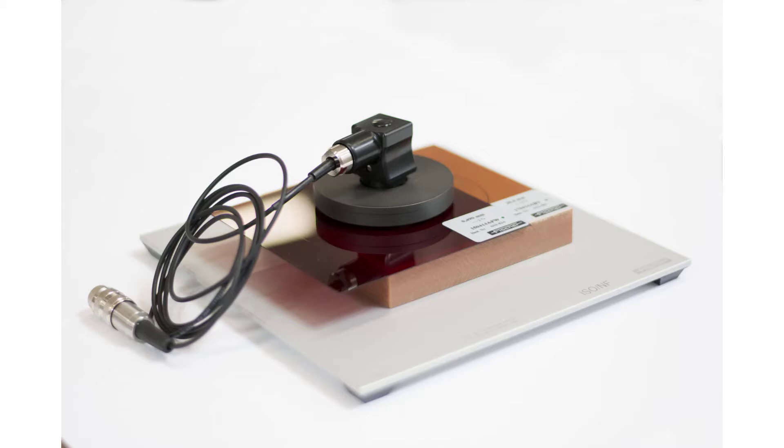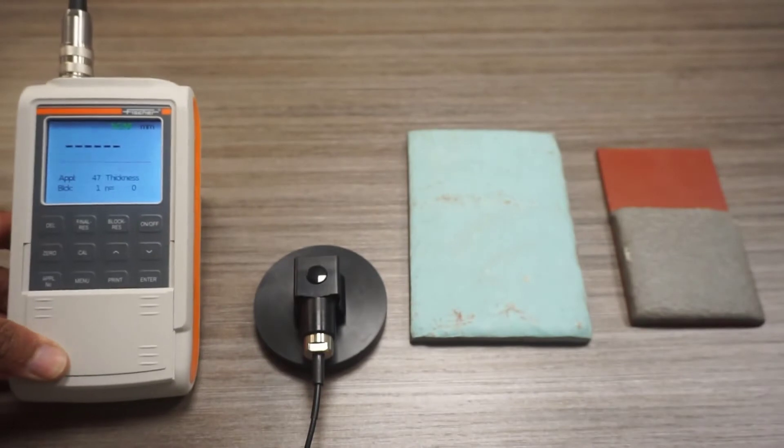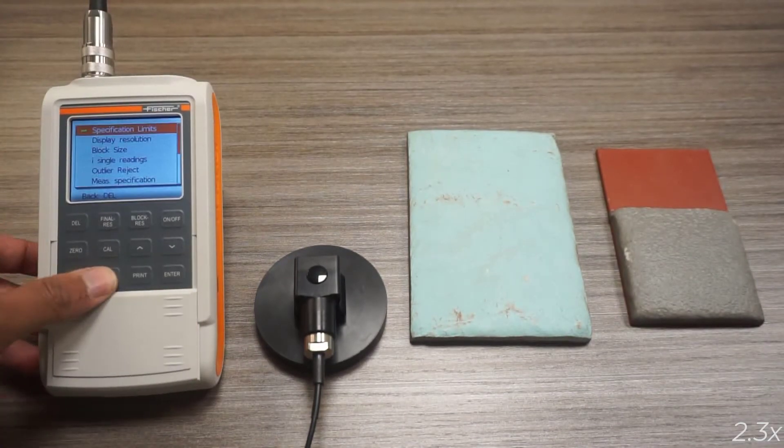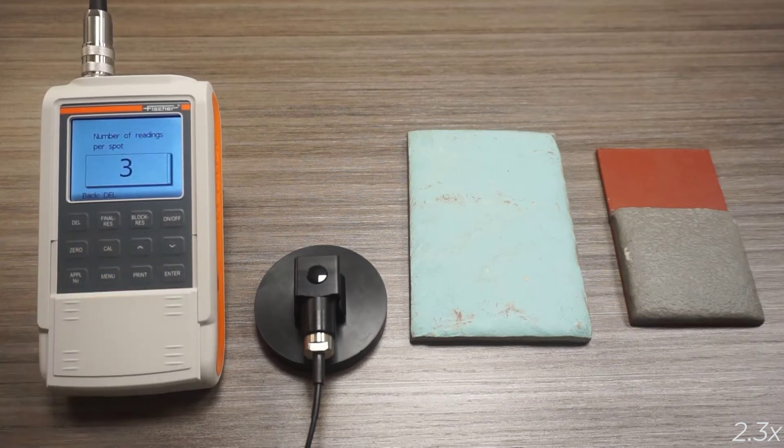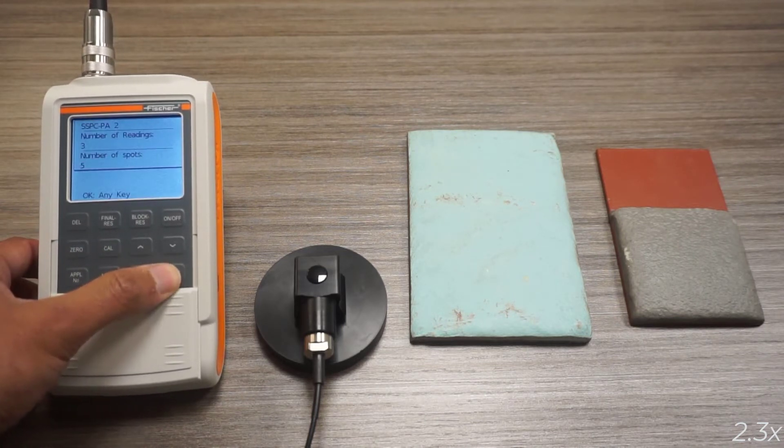The dual scope FMP40's interchangeable probe system offers the flexibility to measure thin as well as thick coatings. An additional feature of the FMP40 is the SSPC PA2 function, which performs and reports the spot measurements required by this industry specification.